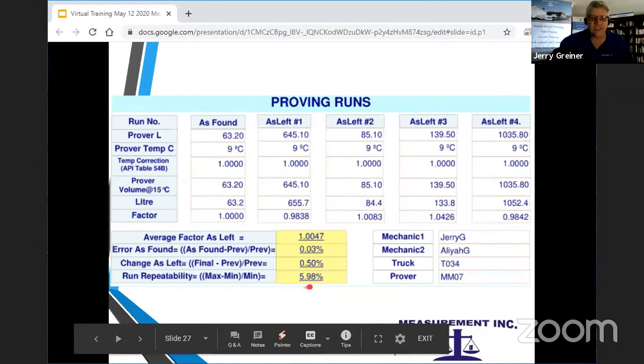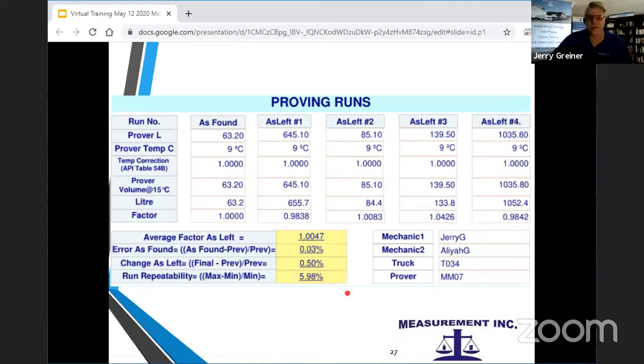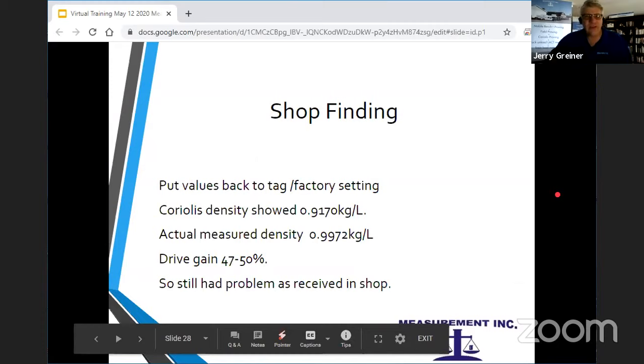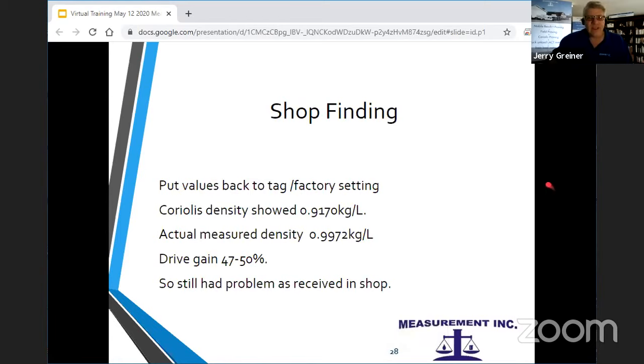Between runs, we still had 6% variance. Our average was really close to what the average should be. So we thought, well, it's in the ballpark, but you can't leave it with 5 or 6% variance. So ultimately, we pulled the meter out and had to do some shop repair work on this. We put the numbers back to the factory settings, and it showed exactly like it was in the field. The Coriolis density was reading about 0.91, 0.92, and really in the shop it was 0.99, just about 1, fresh water. And our drive gain was still in the 47 to 50% range. So there are still problems as received in the shop.